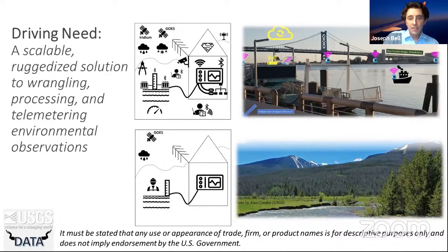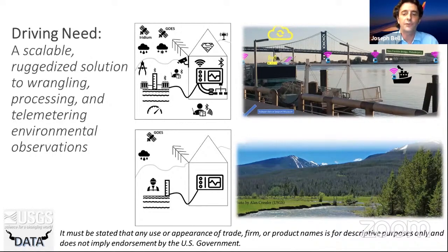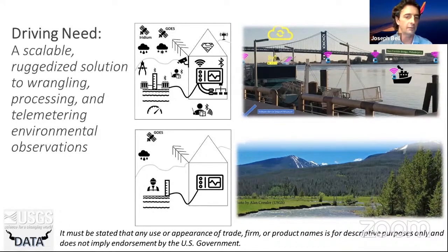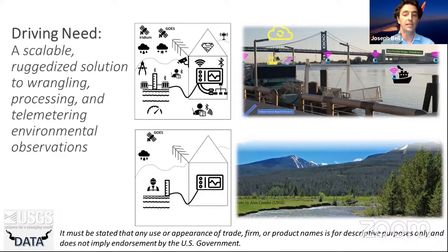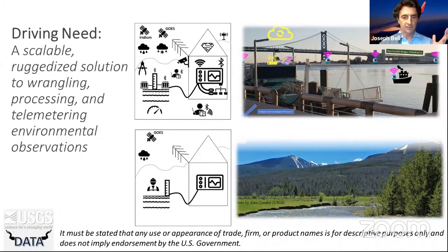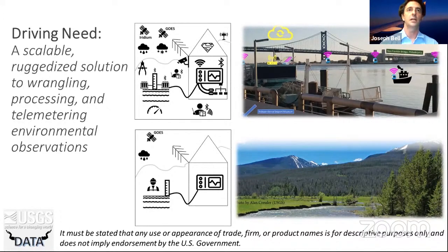When we look at remote deployments in the survey, the predominant go-to protocol for sample collection is SDI-12, and we have to handle this. An exciting technology we've come across from a group called RIOT — Radio Internet of Things — is the ability to wrap SDI-12. They've created a hat that sits on top of an SDI-12 sensor and a receiver hooked into a data logger. The data logger pings that receiver as if it were an SDI-12 unit. The receiver sends the SDI-12 command wrapped in LoRa, the hat translates it back into SDI-12, calls for the observation, then reverses the process and sends the data back. This is a retrofit we feel has a lot of value.